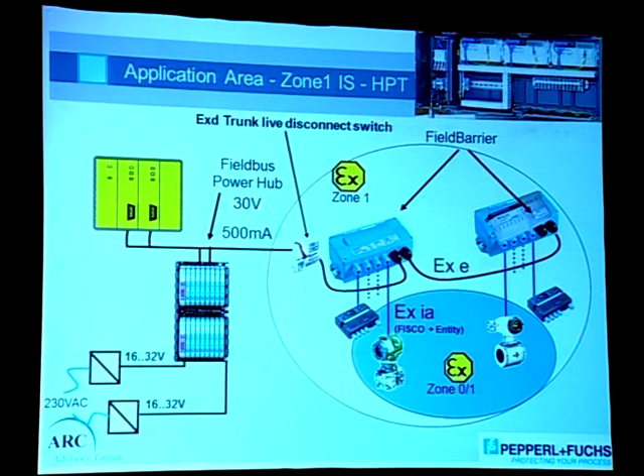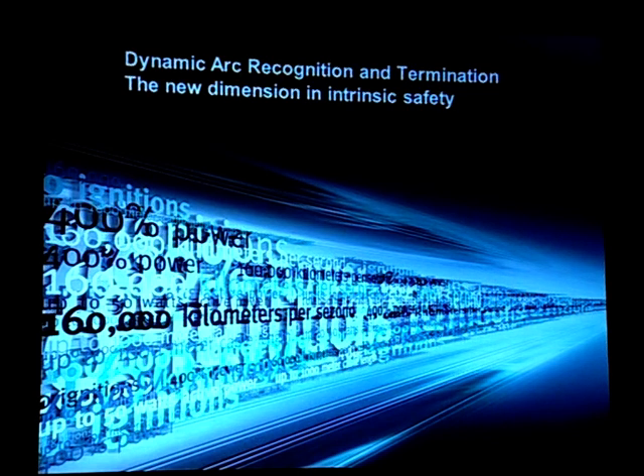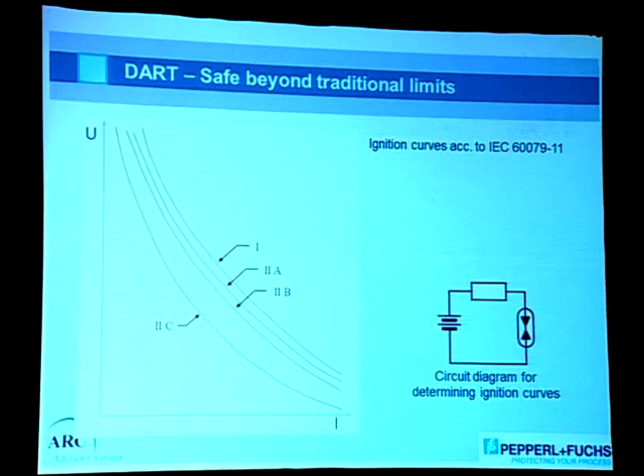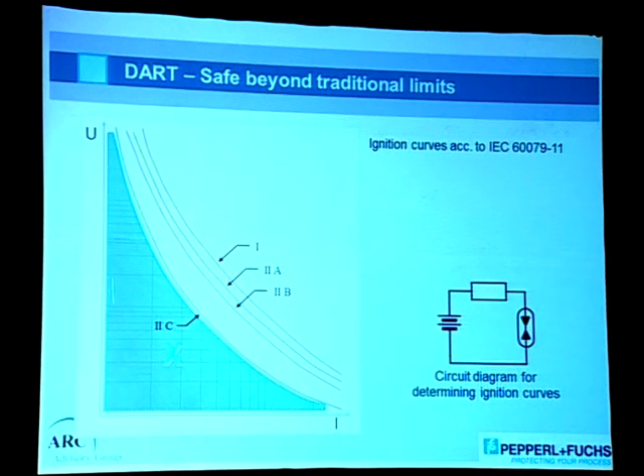What we did is rethink how to achieve intrinsic safety. The main problem is we have to limit the voltage and current, and that's the traditional way of thinking about intrinsic safety. Now we move one step ahead and think in the other direction. This is a different gas group, what we normally encounter in oil and gas, petrochemical industries. What we do is limit the energy. As long as we follow a certain gas group, we limit the energy so it stays below the gas group curve, and the energy is not able to exceed it as long as it stays below the curve.